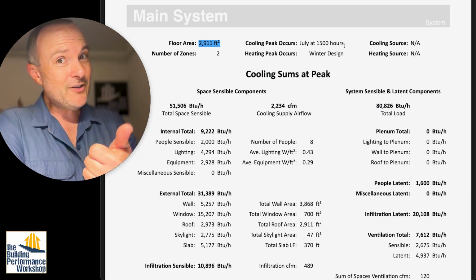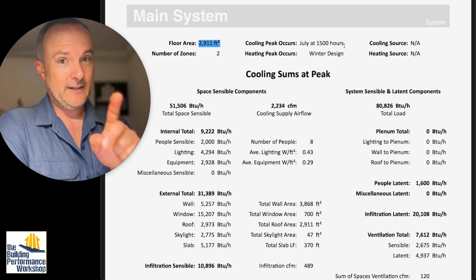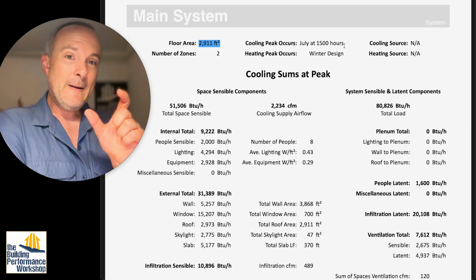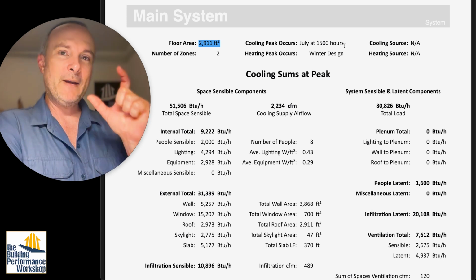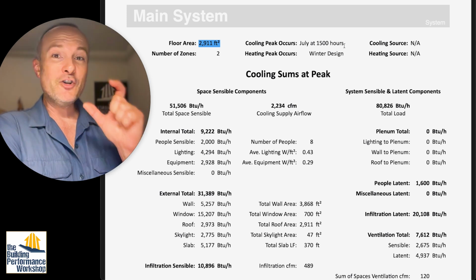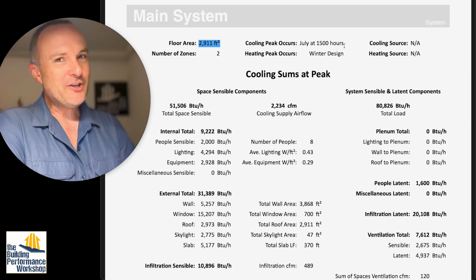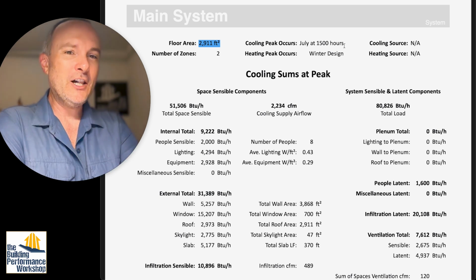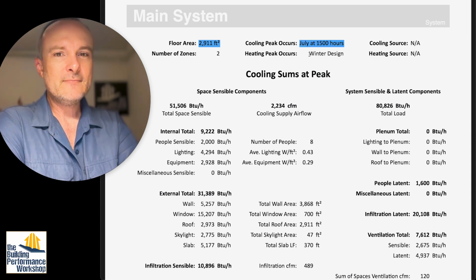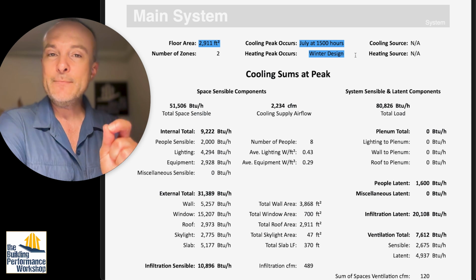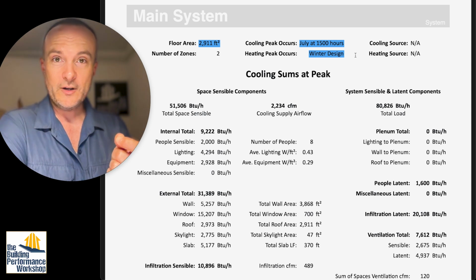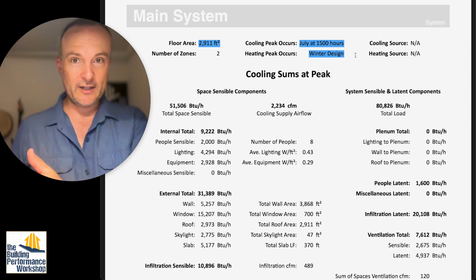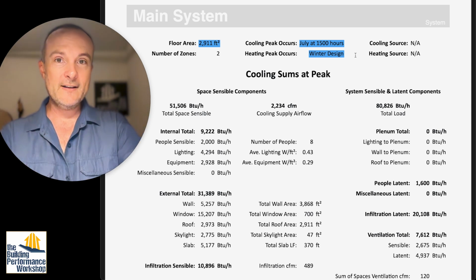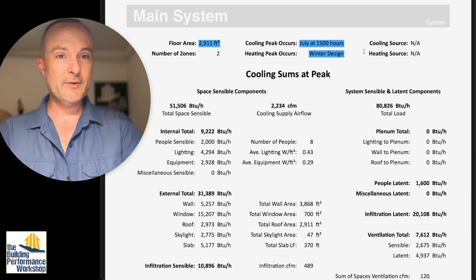Also, in residential land, and commercial land is different, and this is one of the clues that this is a commercial person doing this: in residential land, 5 o'clock is when people are coming home from work or school and cooking. In commercial land, there's no cooking going on inside. So that, I think, is one clue that we're not dealing with somebody who really specializes in residential. Heating peak occurs at winter design temperature. Design temperature, just to remind everybody, is the 99% coldest temperature that you're historically going to experience, not the 100%. And it's explicitly stated in the load calc manuals, like Manual J, not to use the 100%.